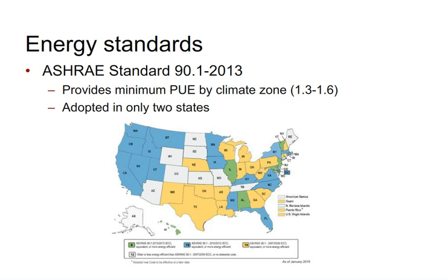Moving on to energy standards — probably you've heard of ASHRAE 90.1. Beyond data centers, ASHRAE 90.1 has been used to benchmark and do compliance methods for energy for a wide variety of facilities. Within the 2013 version, they introduced data centers and started talking about PUE as an energy metric. They gave minimum PUE to be achieved in data centers by climate zone — typically those PUEs would vary between 1.3 and 1.6 as a minimum standard. The 2013 version has only been adopted in a few states.